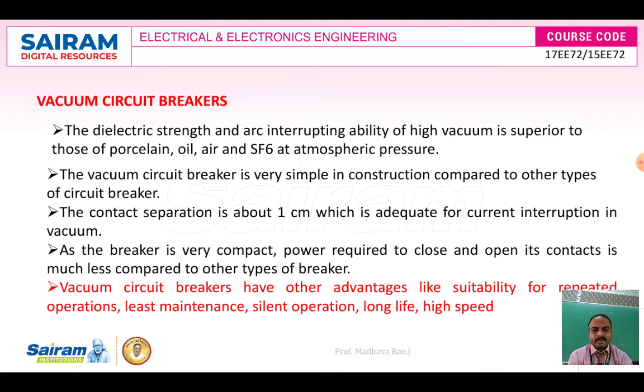So the vacuum circuit breaker has other advantages, like suitability for repeated operations. Repeated operations will not damage anything, so you can use it for repeated operations, and it needs least maintenance. You can call it low maintenance and silent operation. An air blast circuit breaker will produce high noise, but the vacuum circuit breaker will not produce any noise, and it has long life and high speed operation. That's why this vacuum circuit breaker is more popular for low and medium voltages.